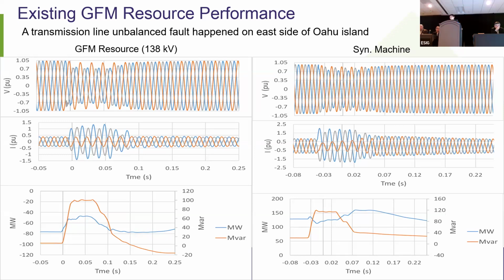On the left-hand side are the grid forming 138 kV resource response curves. The top one is the voltage measured at the 138 kV side POI. You can see two phase voltages get reduced. I think the fault happened between those two phases, and the third phase looks okay. The middle figure is the per-unitized instantaneous current response from this resource. And the lower figure is the P and Q measurement for this resource.